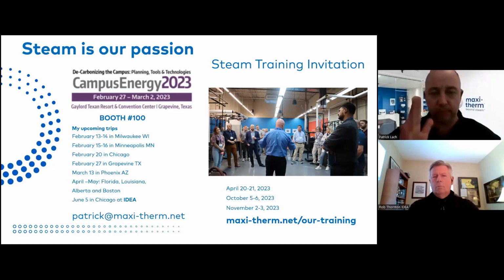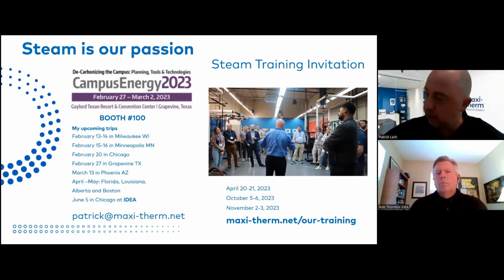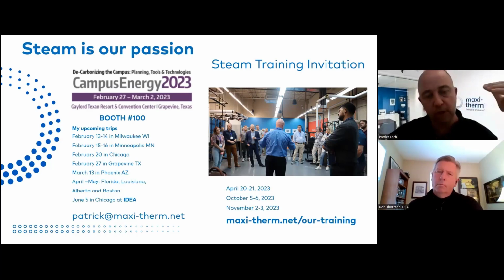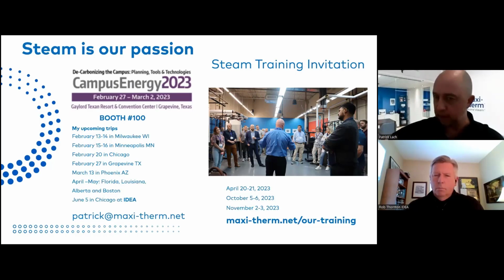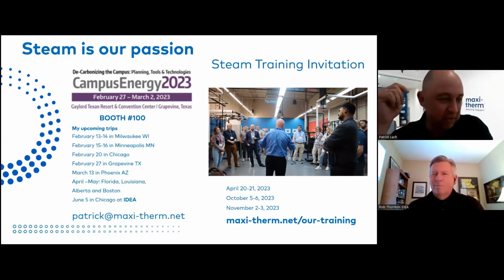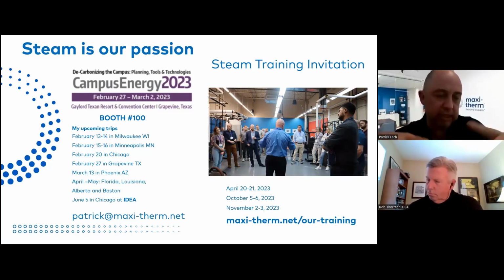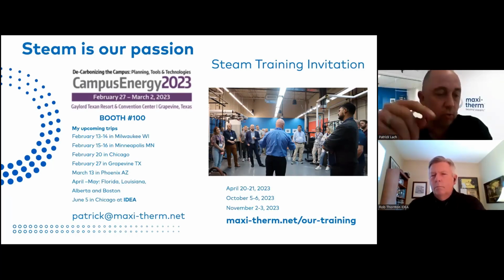I mean, come to our steam training and we'll explain why. I don't want to go over the mechanism of steam traps, but we use bimetallic on high pressure steam or thermostatic on low pressure steam on drip legs. That's what we recommend, to bring the drip legs back to a condensate mixer. So I will not go too much into detail today. Subscribe to our steam training or give me an email or a shout. We have a condensate mixer, which is basically a sparger with a multitude of orifices that we size based on the max loads and pressures. And you can bring multiple drip legs, I mean, steam trap drip legs, to one condensate mixer.